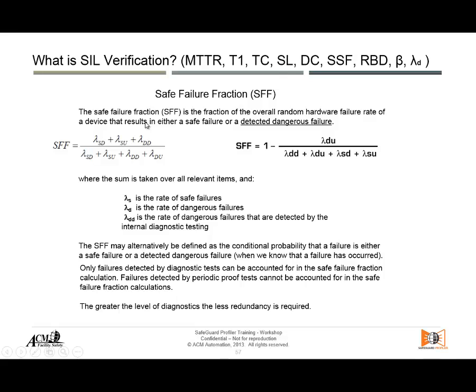Safe failure fraction. So the safe failure fraction is the fraction of the overall random hardware failure rate of a device that results in either a safe failure or a detected dangerous failure, right? So we talked about that already. There are safe failures, detected or undetected. They're nonetheless safe or spurious, and then we add the detected dangerous ones that we get through diagnostic coverage. So diagnostic coverage has an influence on the safe failure fraction.